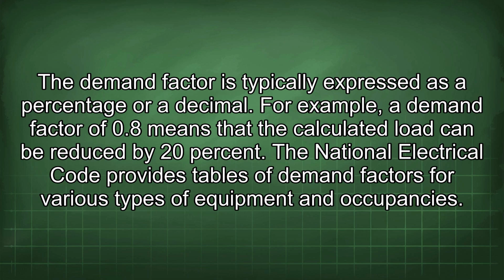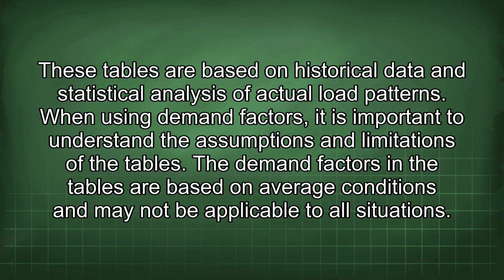For example, a demand factor of 0.8 means that the calculated load can be reduced by 20%. The National Electrical Code provides tables of demand factors for various types of equipment and occupancies. These tables are based on historical data and statistical analysis of actual load patterns. When using demand factors, it is important to understand the assumptions and limitations of the tables.